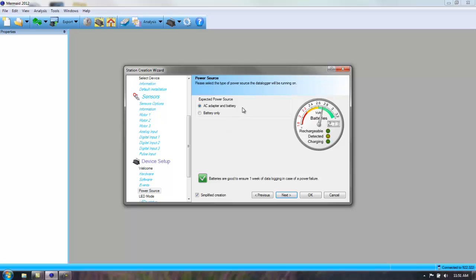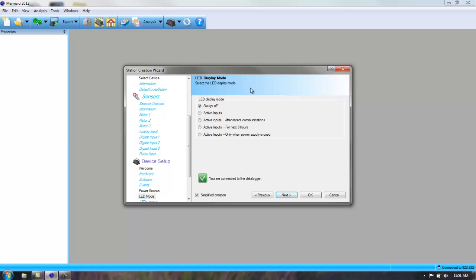But for this station, I'm going to go ahead and connect up to the duplex power outlet, and I'm going to use my AC power adapter, and I'm going to select it there, and I hit next. The LED mode is actually how you want your communication LED to flash or blink. And what I like to use on this particular station is activate my inputs only when the power supply is used. The reason behind this is that when I'm connected up to the duplex for my AC power and it's good, I have good AC coming to my data logger, I will have a blinking light. This way I don't need a multimeter to check to see if my duplex is good. Then hit next.